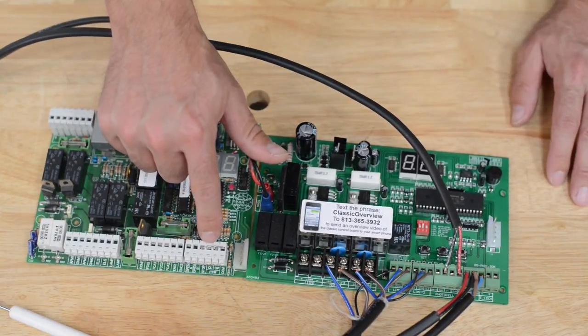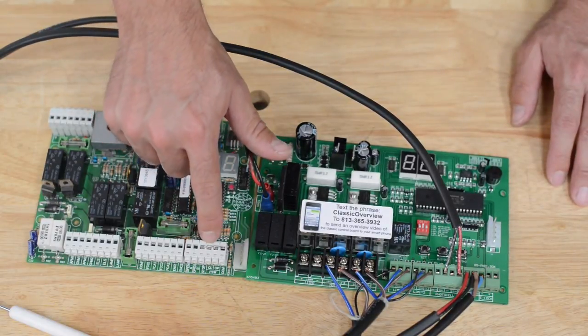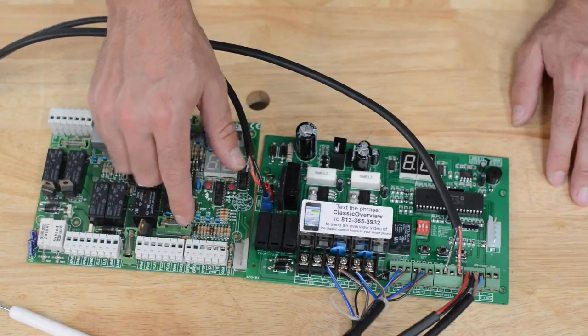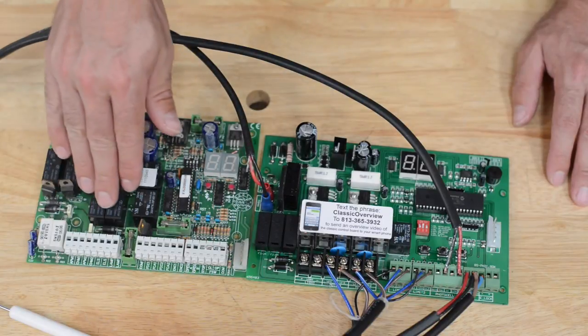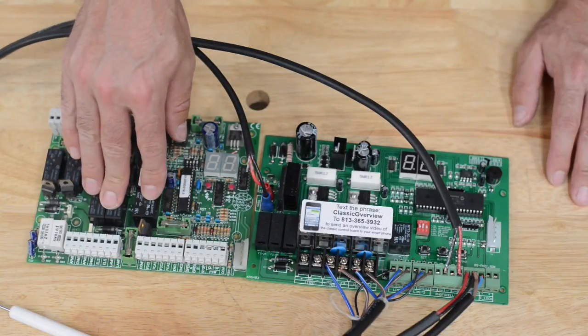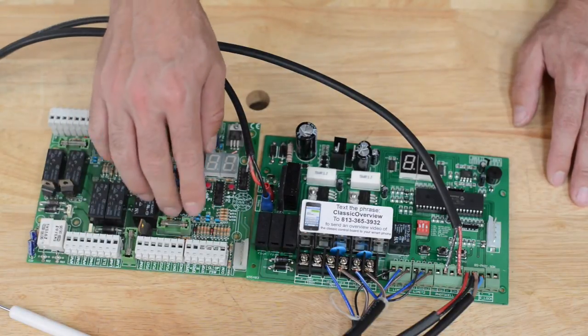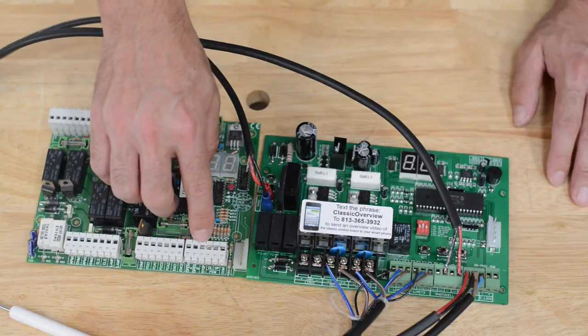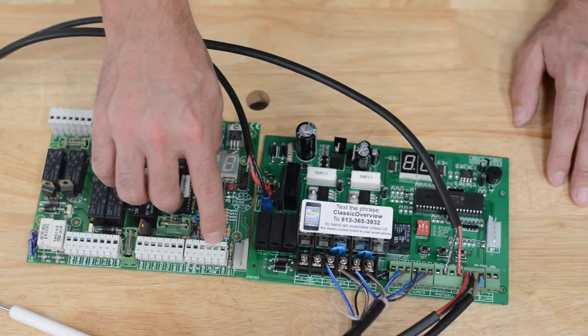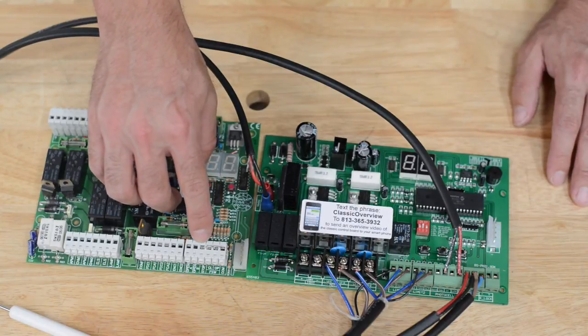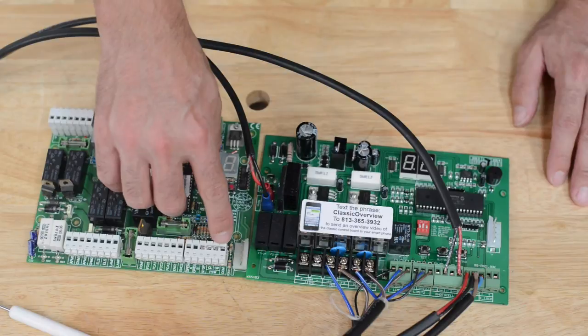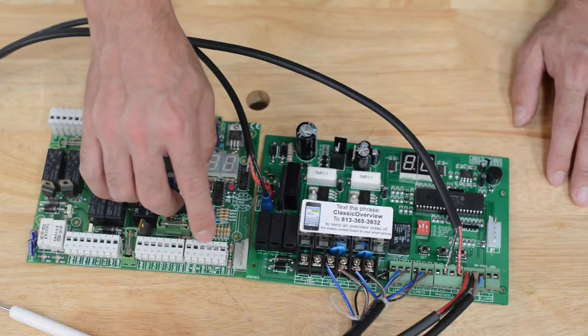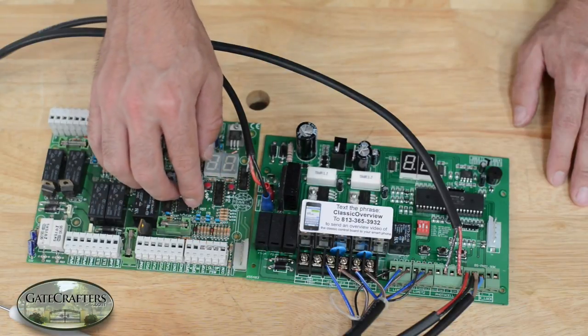Lastly, we have our safety devices or our safety jumpers. On the old ES1600 board, there's actually three different safety terminals: stop, open safety, and close safety. All three of which will be jumped to common in order to operate if you don't have any safety devices.